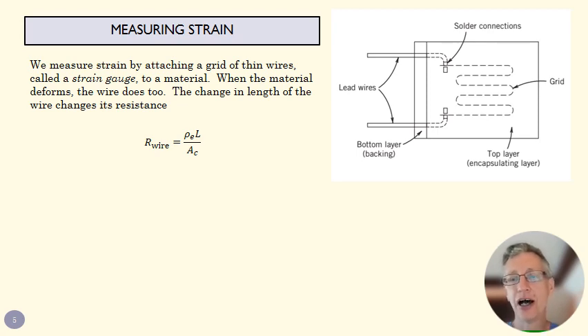A strain gauge is essentially a really long wire that's lapped back and forth and we attach that to the material such that when the material deforms, when it changes its length, the surface of that beam changes its length and the length of this wire changes as well.